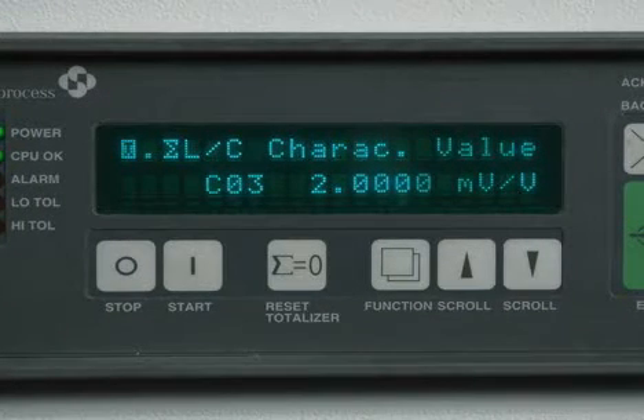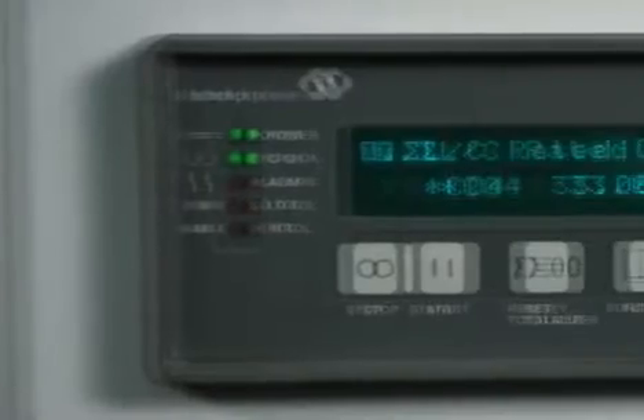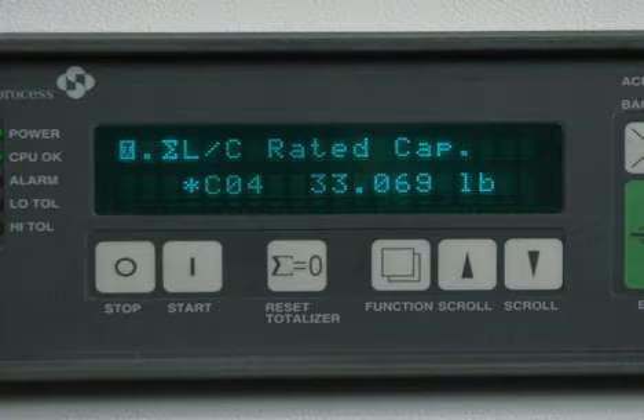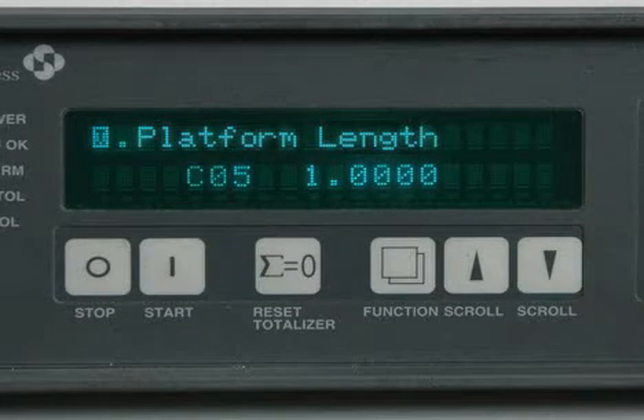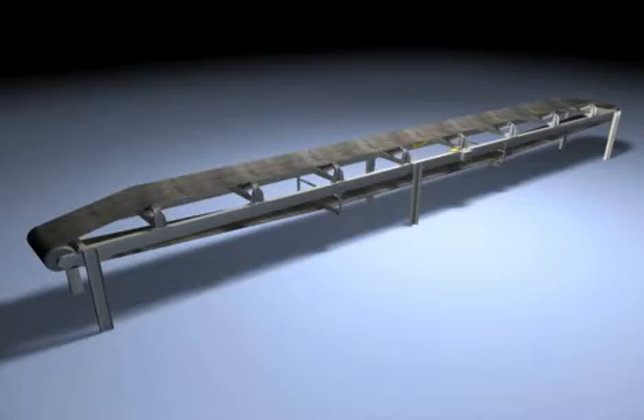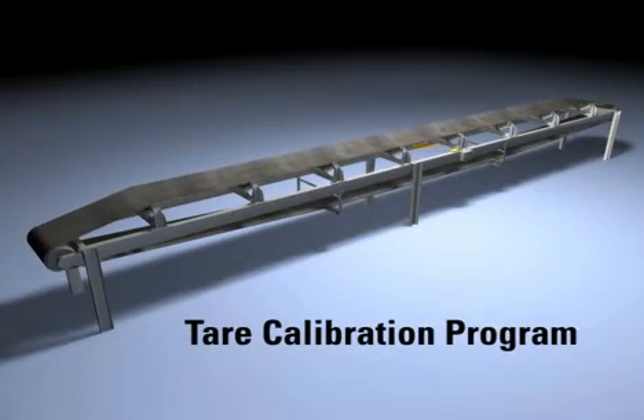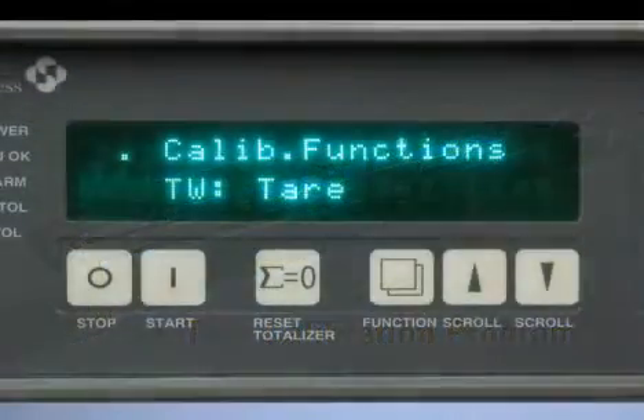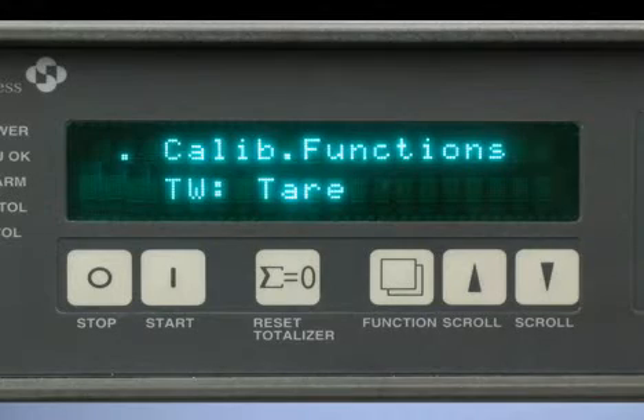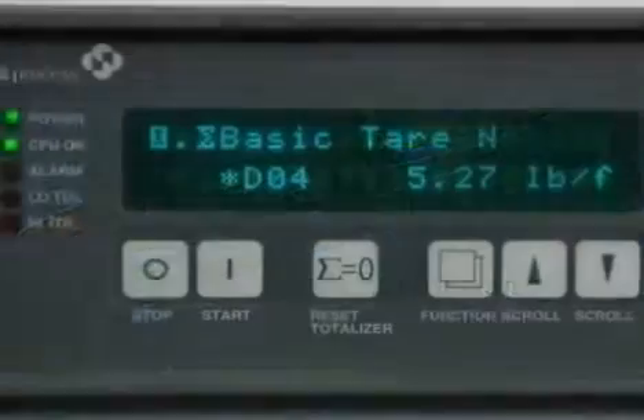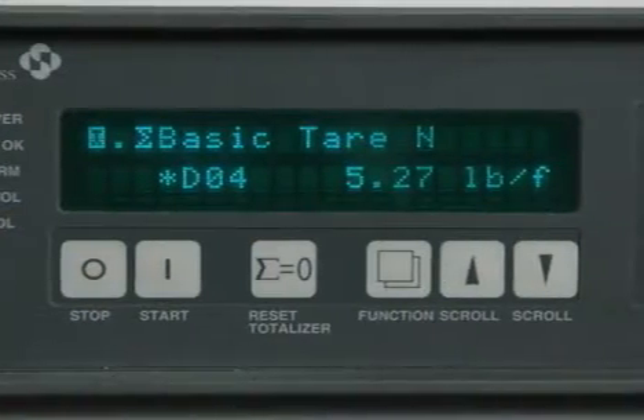Before moving to the next step, make sure some important parameters are entered correctly. Check the values for C03, C04, and C05 on the LCD screen. The correct values may be found on the equipment or on the system design sheet. After the check is complete, start the system and run the tare calibration program. This program will calibrate the tare weight over 1 belt revolution. The resulting number can be checked in the basic tare section of the LCD menu.